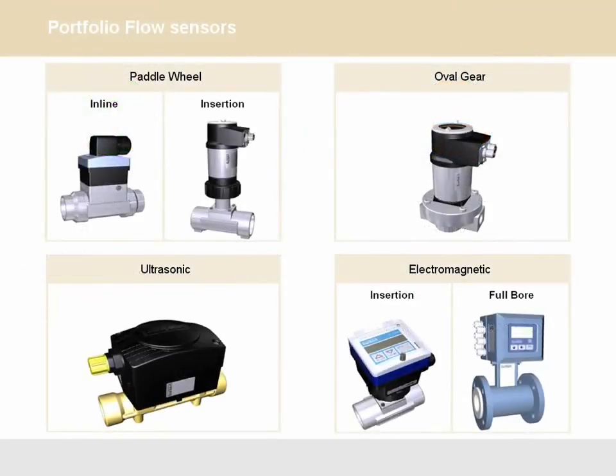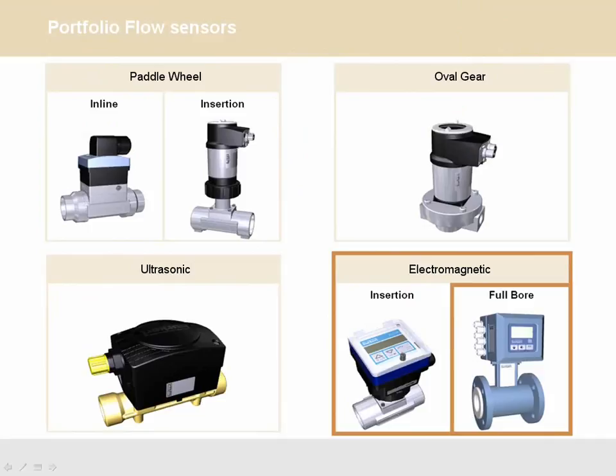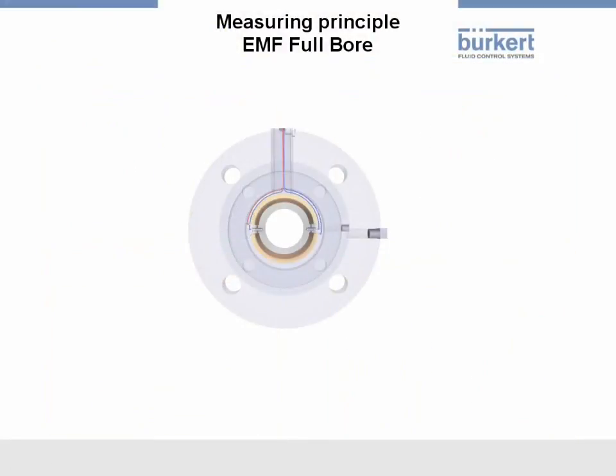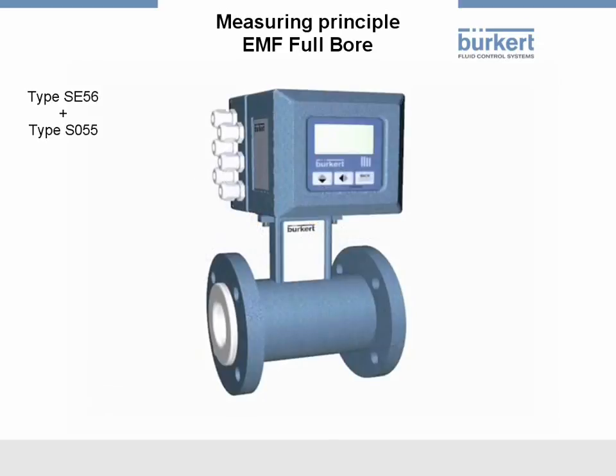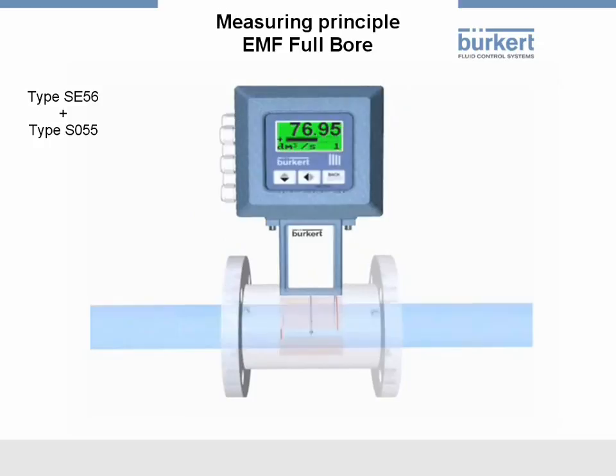Now let's turn our attention to the full-bore method. In full-bore measuring, also known as full-bore EMF, two electric coils and two electrodes are positioned around the measuring pipe. Both coils generate a constant and homogeneous alternating magnetic field in the entire flow cross-section. If a conductive fluid flows through the magnetic field, a current is induced in the medium. Now the voltage can be measured at the two electrodes. The higher the flow speed, the higher is the induced current, and therefore the measured voltage. The voltage signal is converted by the electronics to standard signals, such as pulses or milliamperes.